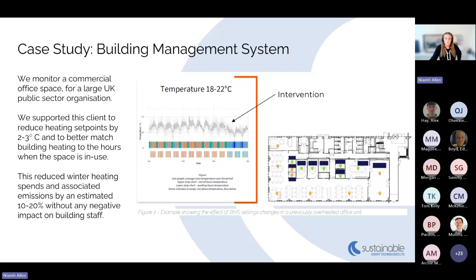They've renewed for their 3rd or 4th year license recently because the data told them something they didn't know. Very quickly they used the data to bring back the BMS and HVAC engineers, because the heating set points weren't adjusted correctly. They'd been set at what it should have been set at, but it wasn't right for that particular building. So we reduced their winter heating spend by about 20% of their emissions, with no impact on staff because we also had all the environmental data. The data was really useful to send to the HVAC and BMS to say, please will you come back and look at the data, it's not quite operating as we'd like. The orange is where we were flagging that as amber, and it was being overheated and underheated in certain areas.